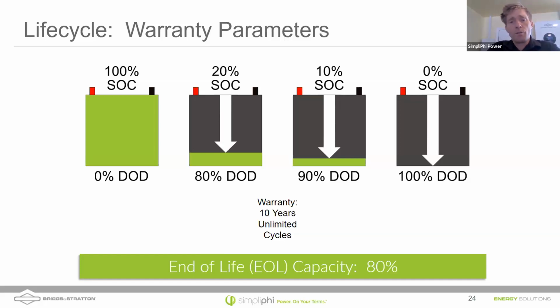If you discharge down to a 90% depth of discharge, we're expecting somewhere between 5,000 to 6,000 cycles out of that battery. But if you just save a little bit more of the energy in that battery, or oversize your bank a little bit and discharge at 80% depth of discharge, we're expecting 10,000 cycles. Again, that's about 27 years. It's a very long time. And so we do recommend customers that are cycling daily, like I do, to choose an 80% depth of discharge.